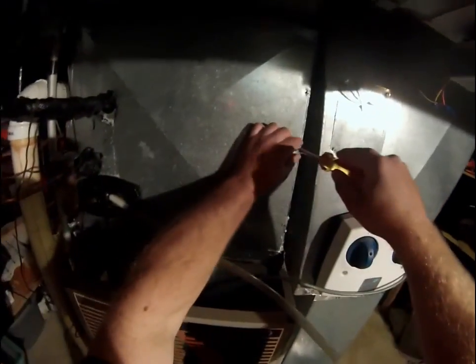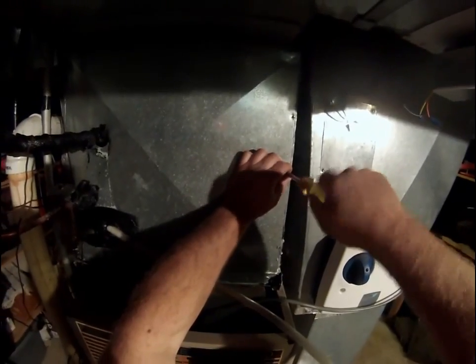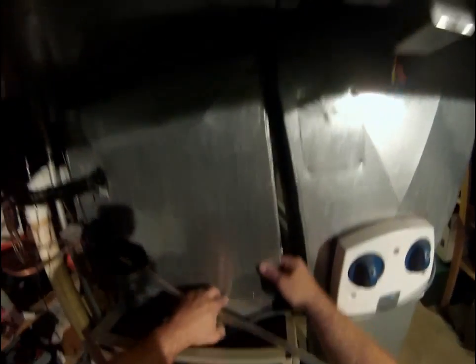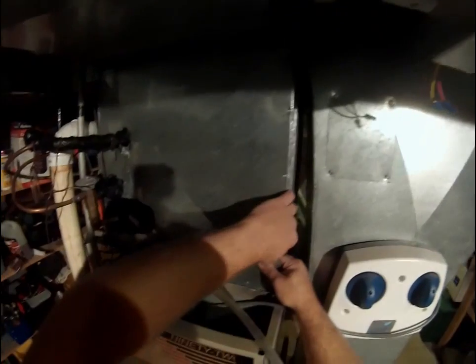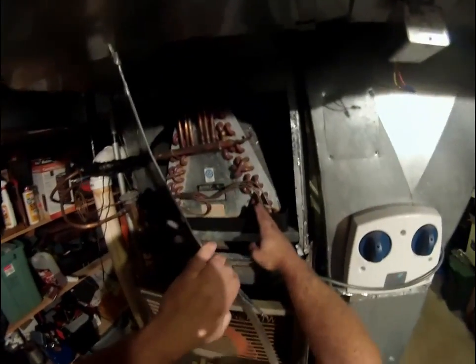The other coil that can get plugged up is called your evaporator coil. And that typically sits in the ductwork or behind a panel somewhere. You just got to kind of use your own judgment to hunt it down, but if that ends up getting plugged up, that will also restrict airflow. Now I've taken a lot of these screws out of here. In this case, I've got to pull a panel off to the side. So you pull this to the side and you can see, here's your air conditioning coil.